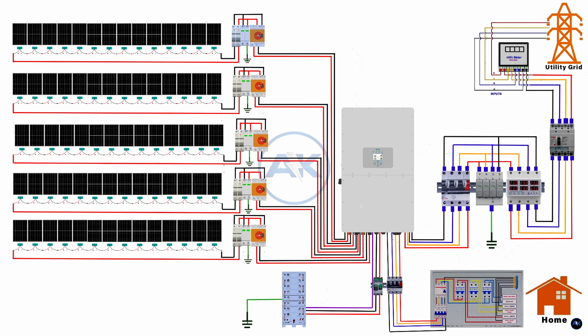Before powering up, double-check all AC connections, confirm grounding is secure, verify correct breaker ratings, and ensure all isolators are in the off position. This completes the AC side electrical connections from the grid to the inverter and from the inverter to the building loads.